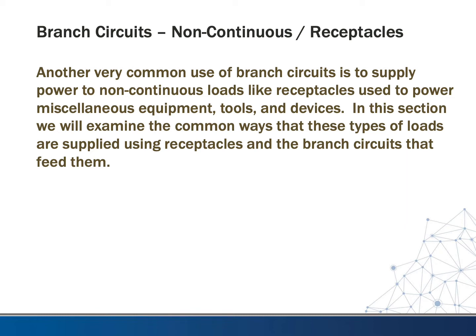We looked at continuous loads — probably the most common is lighting — last time. This time we want to look at another very common use of the branch circuit: to supply a non-continuous load. This is anything that we expect to not be energized for more than three hours — three hours or less continuously energized is non-continuous.